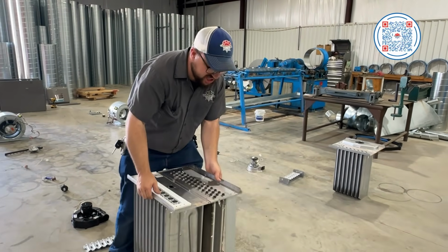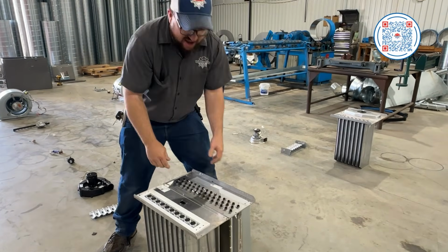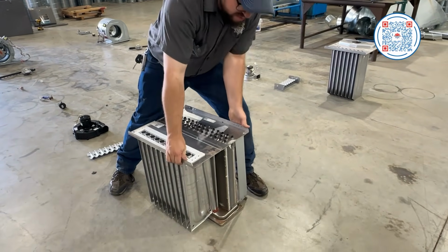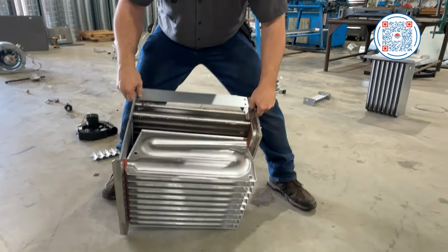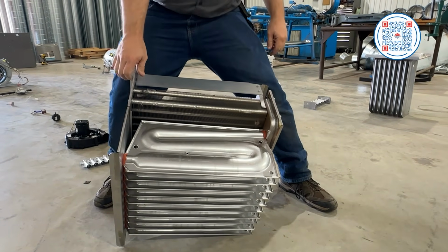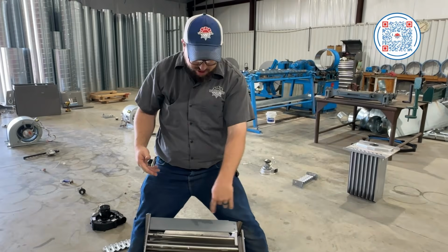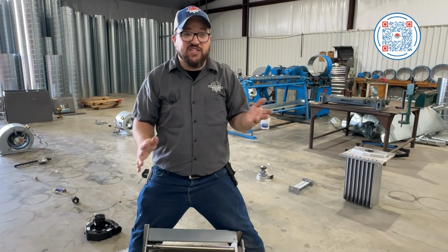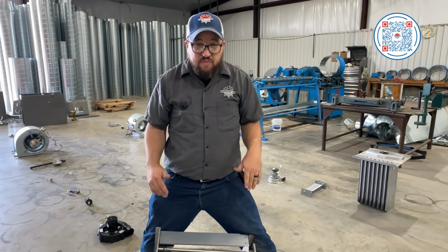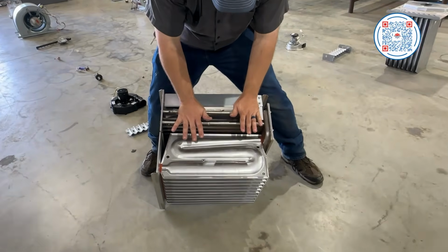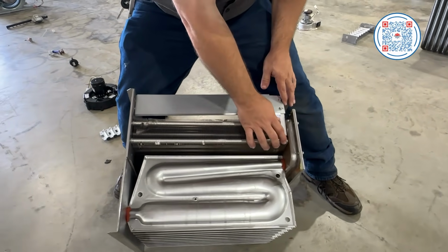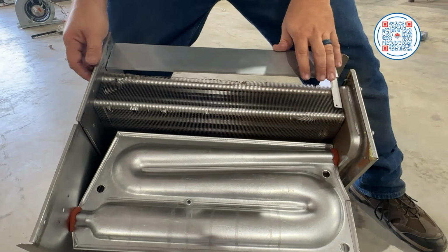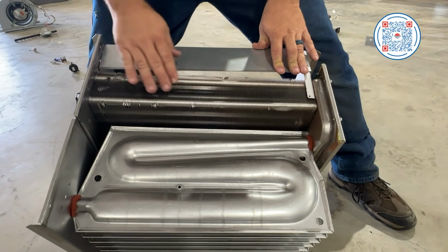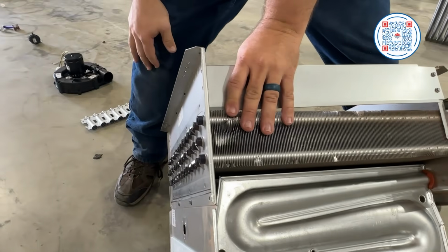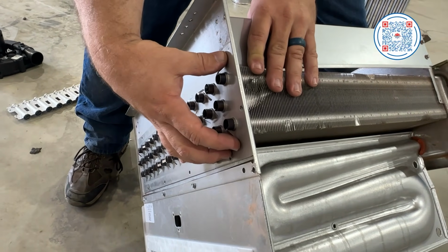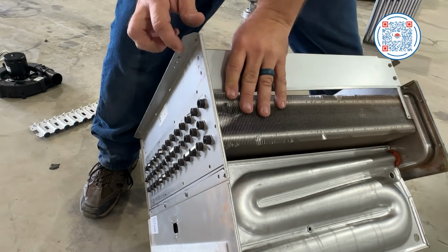And it is all there. You can see we are just building on the same concepts. Everything started with direct draft having ribbon burners that go down here, and then the flame would just go up. Well, we achieved getting better efficiency by having it go through a tube and having an inducer that pulled some of that air out, at least pulled it through there. And those were actually still not considered positive pressure inducers. After that, they decided, well, we want to get more efficient. So how are we going to get more efficient? We need to have it go through more of a heat exchanger. And so they added what we call a secondary heat exchanger, also called a condensing heat exchanger. And that's where all the flues go back here, and then it goes through here again, and then it comes out right here. And we actually have a special, what we call a cold header. It's plastic so that you're not going to rust up anything.